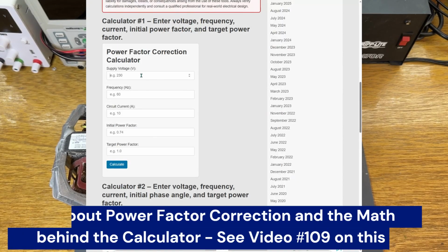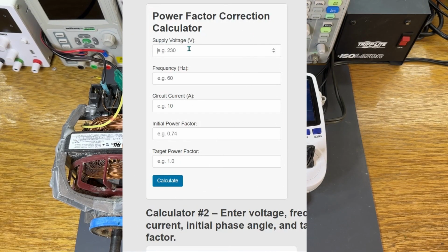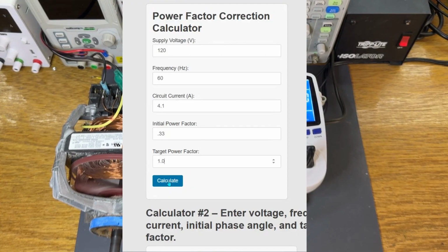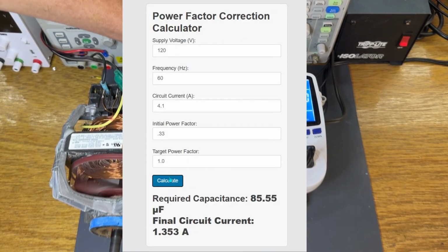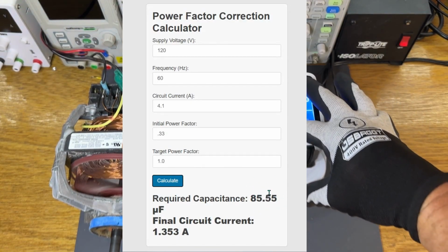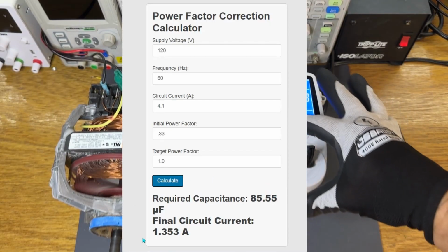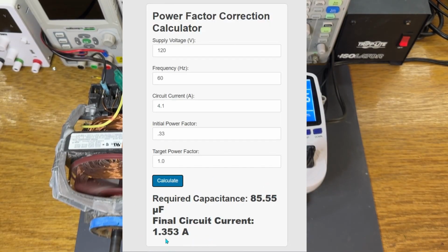In the calculator, I'll enter the supply voltage of 120 volts, the frequency of 60 Hz, the current draw of 4.1 amps, the reported power factor of 0.33, and the desired power factor of 1.0, which is a perfect power factor. And here's our result. The calculator tells us that a capacitor value of around 85 microfarads should bring us to unity or perfect power factor of 1.0. It also tells us what the expected current draw will be once power factor is corrected, which you can see is less than 1.5 amps.